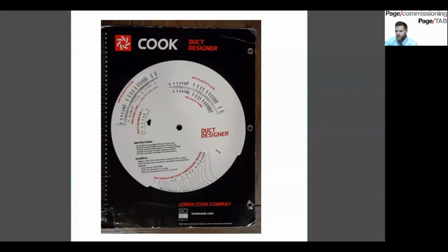The two main ones that you're going to be seeing are low pressure or medium pressure, with low pressure being the majority. So if it's low pressure, it's going to be a 0.08 friction loss. And if it's medium pressure, it's going to be about a 0.2. And then you can check the ductwork based on that.